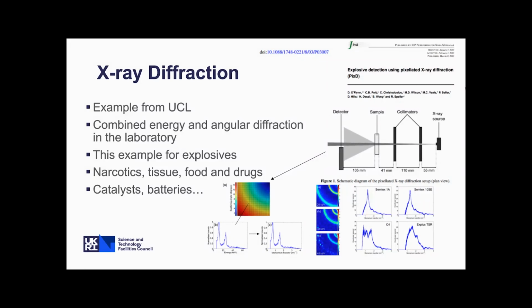And again, it isn't just a synchrotron technique. So this is a diffraction technique that's been conducted at UCL mainly. So here they're using collimators on a conventional X-ray source to give a point source on a sample. Then HEXITEC is positioned off axis, and that point then gives you the diffraction pattern at different angles across the detector. So you get different energies, you'll get rings at different positions from the sample. And you can combine the energy dispersive diffraction pattern on each pixel to get you a single spectrum.